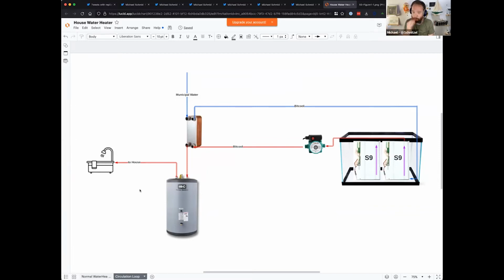The only thing I usually do, because when you buy the miners, they usually ran for a couple of years in an air environment, so they're very dirty, is clean them with the BitCool itself. You just brush them off. What could be dangerous is if you have a shaving of metal or something that gets into the BitCool, since it's now transferring through the whole system, it could touch a piece of the PCB and create a short. So you want to make sure all the dust and stuff is off, but that's it. You don't have to modify the miners in a specific way, you just put them in.